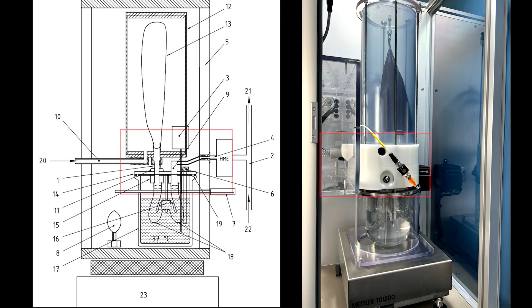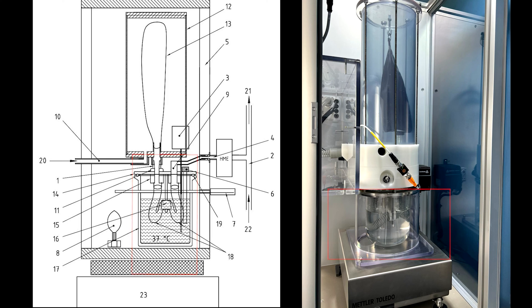Beneath that is the valve housing where a series of directional valves control the flow of air through the humidity generator. Lastly we have the heated water bath which controls the water temperature per the guidelines in the standard.